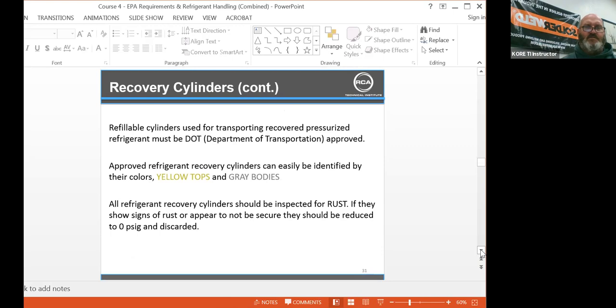Refillable cylinders used for transporting recovered pressurized refrigerant must be DOT approved, which they are. That is handled by our recovery company. Approved refrigerant recovery cylinders can be identified by their yellow top and gray bodies. All refrigerant recovery cylinders must be inspected for rust. If they show signs of rust or appear to not be secure, they may be reduced to 0 psi and discarded.